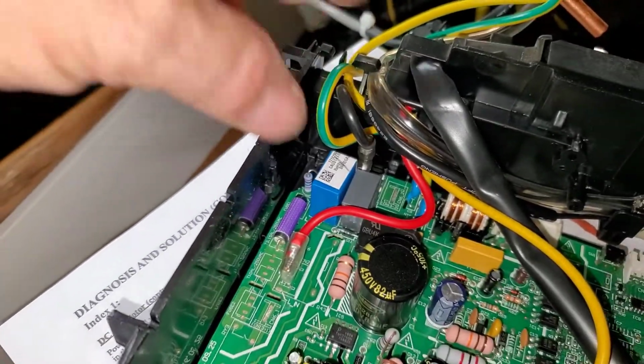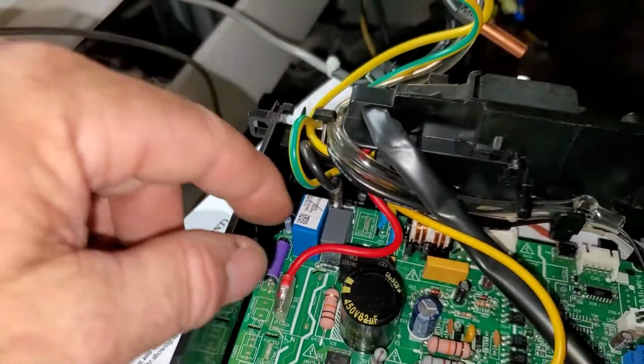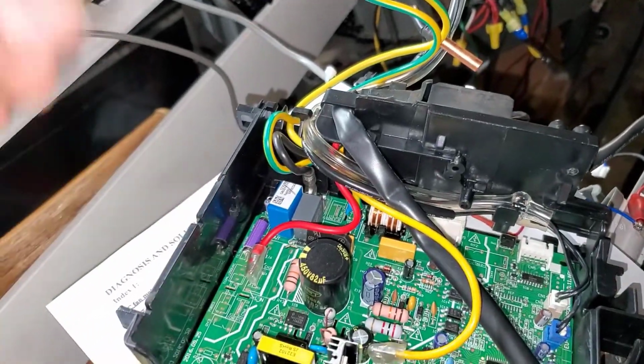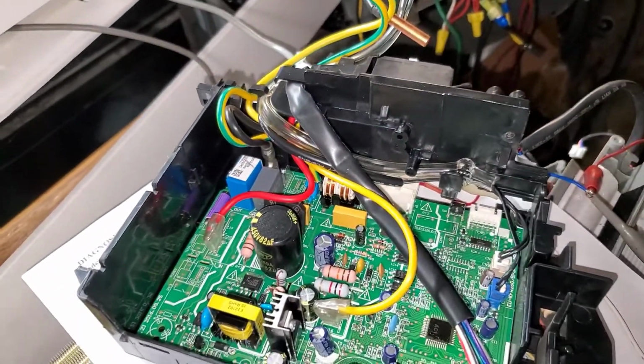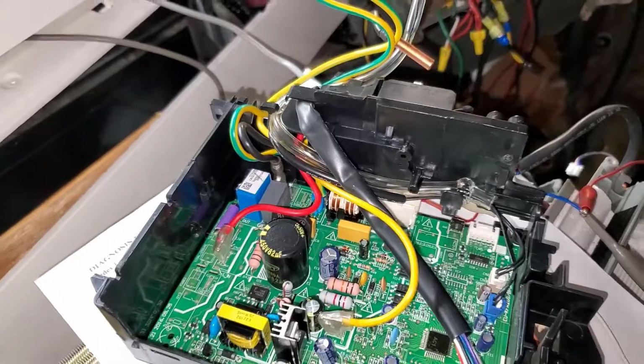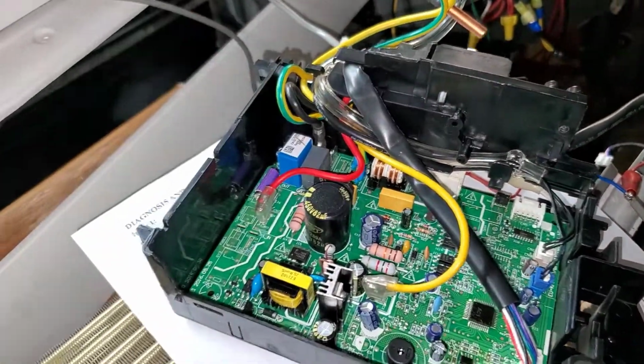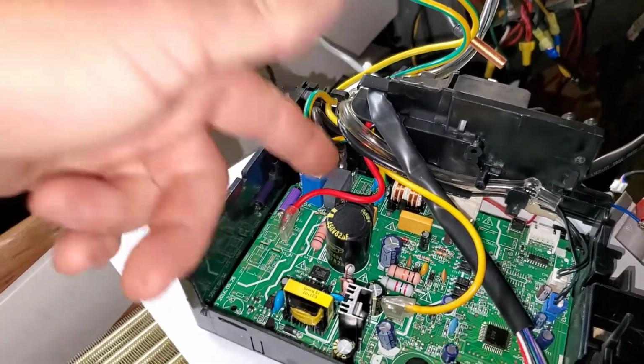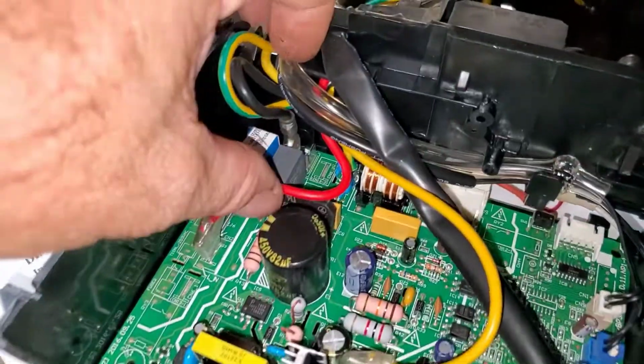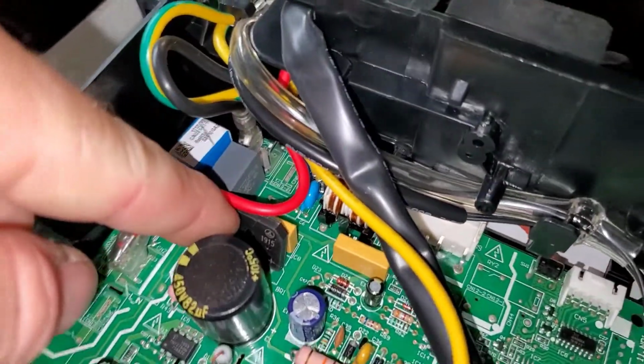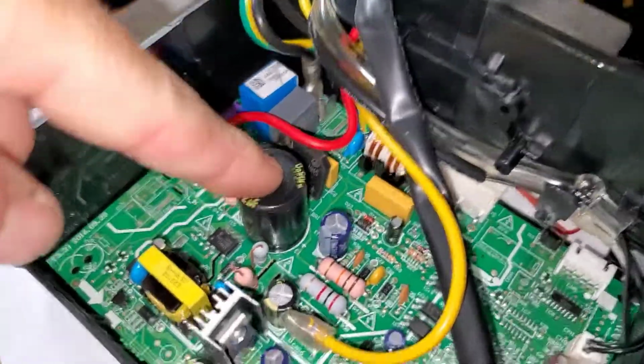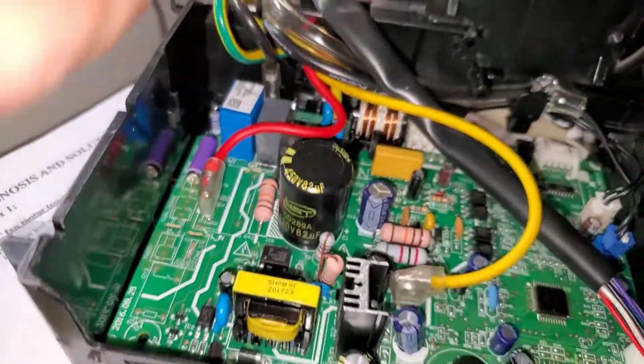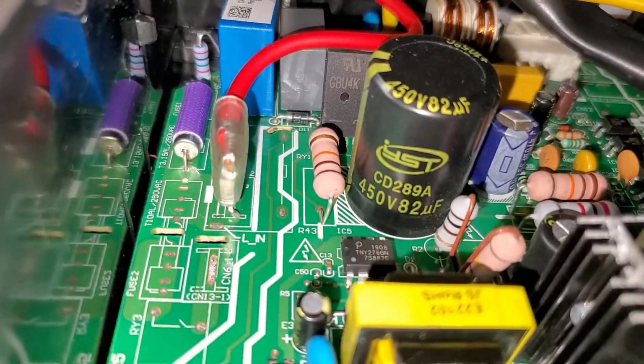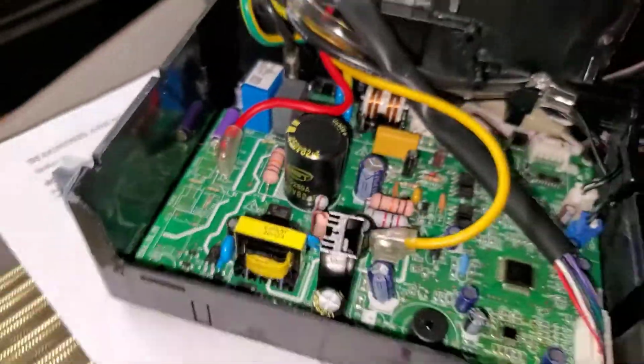It probably charges up a little capacitor until it gets to a certain level and the relay closes. At least that's how a lot of these kinds of power supplies work, so it doesn't have that inrush current. When the capacitor is at zero, it starts to charge the capacitor up, and then the relay closes and charges it the rest of the way. It goes right through the bridge rectifier there into the capacitor. Just that capacitor for the blower motor. The blower motor doesn't take all that much. It's a 450 volt rated capacitor.